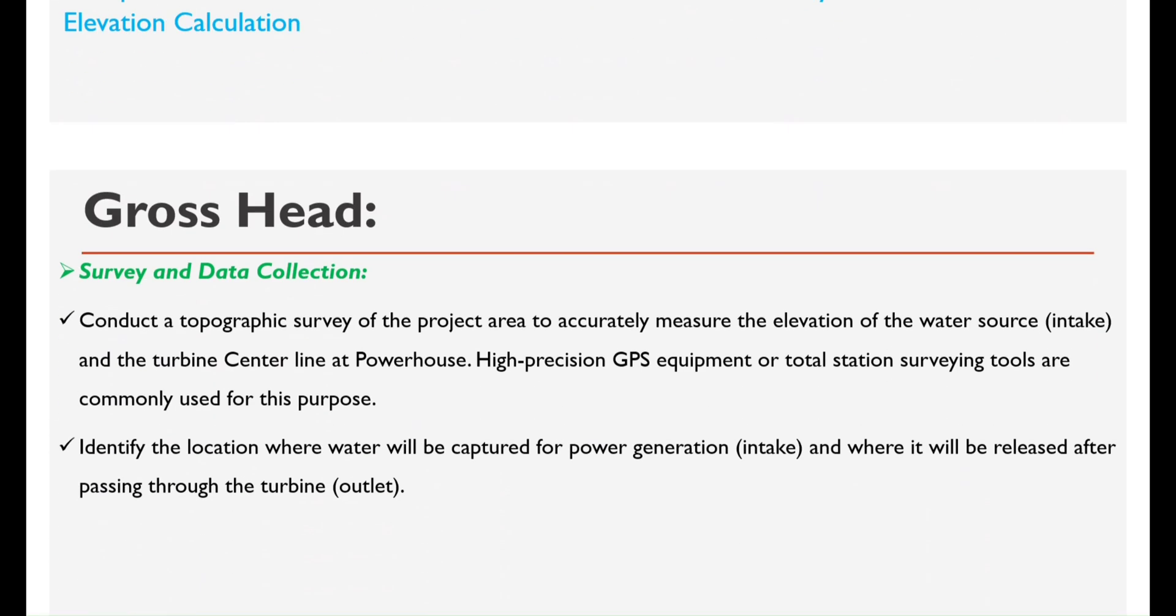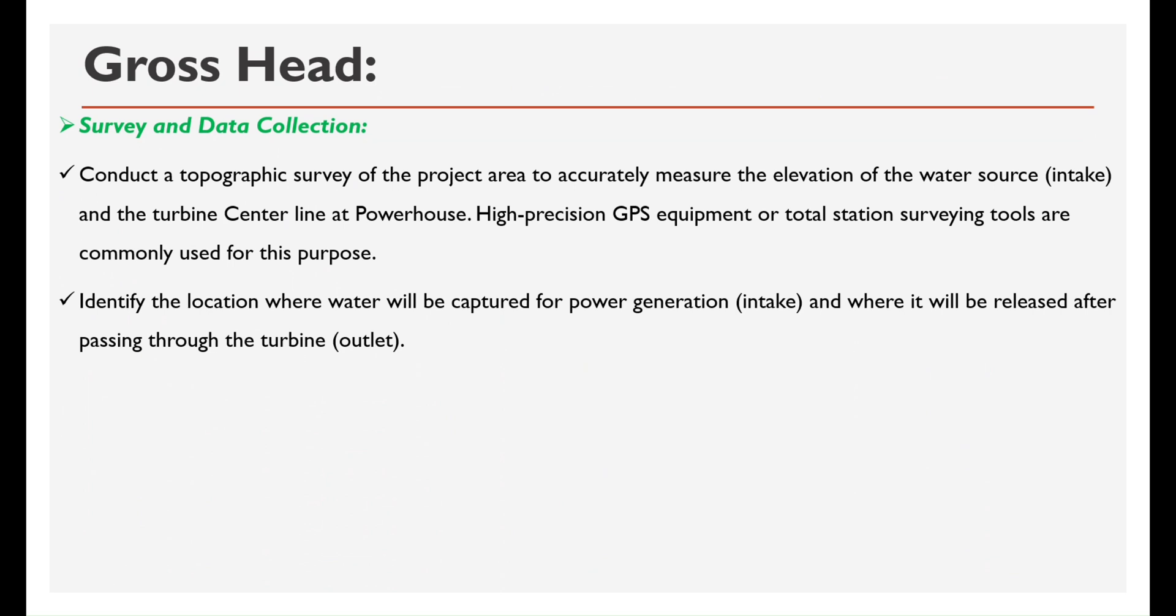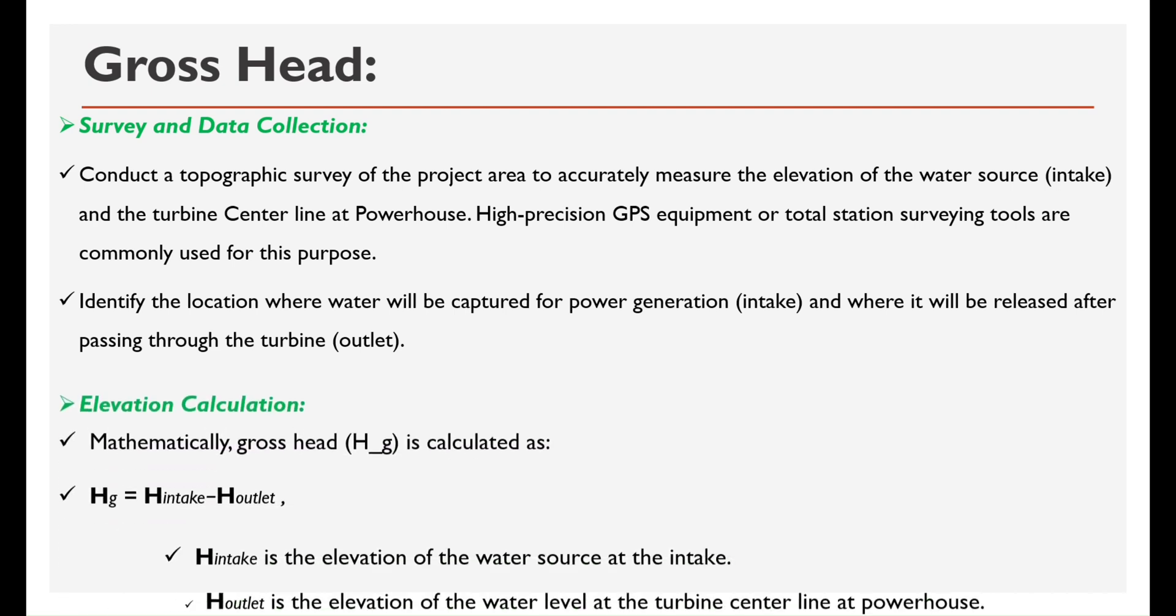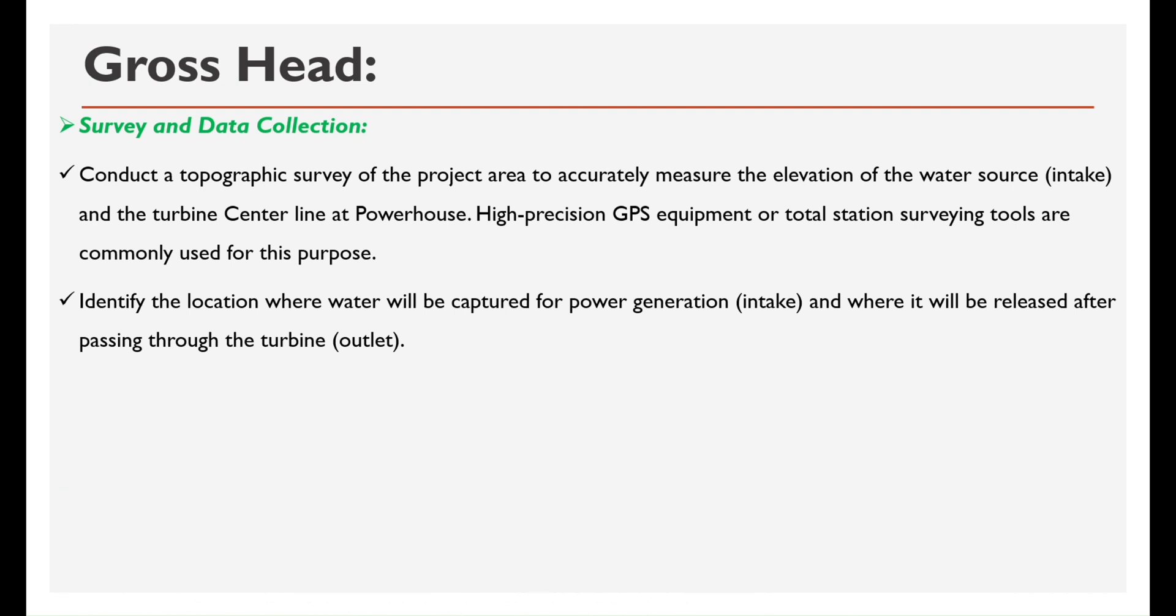Survey and data collection: Conduct a topographic survey of the project area to accurately measure the elevation of the water source and the turbine center line at powerhouse. High-precision GPS equipment or total station surveying tools are commonly used for this purpose. Identify the location where water will be captured for power generation and where it will be released after passing through the turbine.